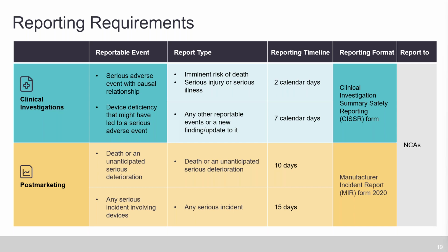The MIR form is usually integrated. You can generate it like a CIOMS or a MedWatch form from the safety database, Argus or ARISg. It has to be configured there, and then the reporting requirements can be taken care of. The clinical investigation summary safety reporting form is a manual form, available on the EU website, that needs to be used for the clinical investigation.